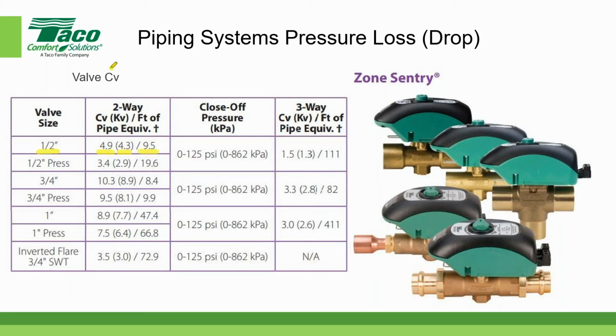And again, the valve CV comes from the manufacturer. In this case, it's us from Taco, but every manufacturer that makes a control valve will publish the CV values. They should publish it. It's not something you should calculate or can calculate. They do it by taking measurements in their laboratory. Okay. All right. So now that we've gone through some of that basic stuff, we get that fun stuff out of the way.